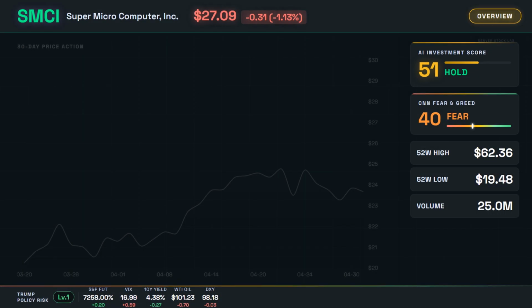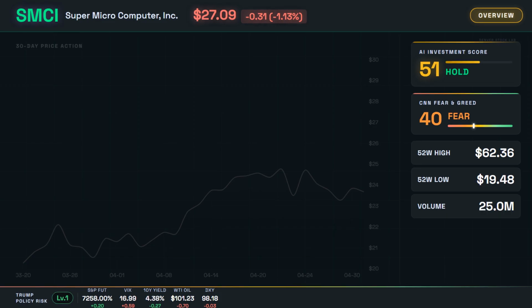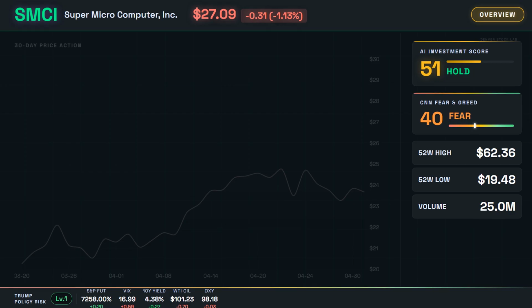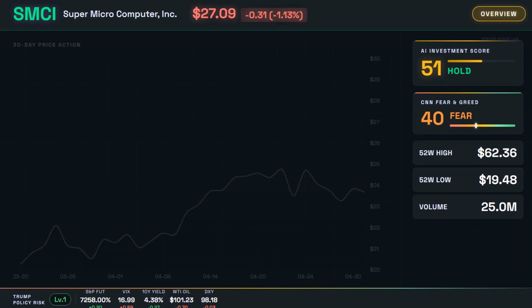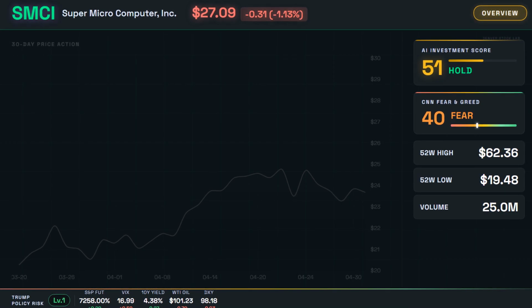Dell is catching up, but SMCI's lead in liquid cooling manifolds, the distribution units that regulate coolant flow, gives them a 20% lead in deployment speed. However, the engineering risk lies in the CDU, coolant distribution unit, the pump and heat exchanger system, where component shortages could cap revenue before Tuesday's earnings.